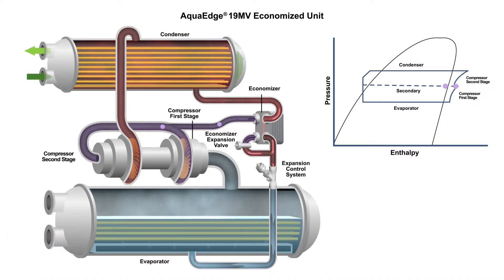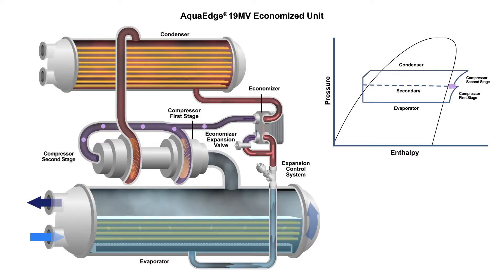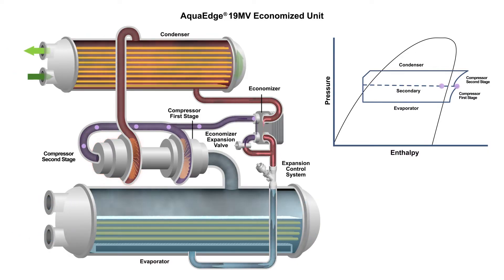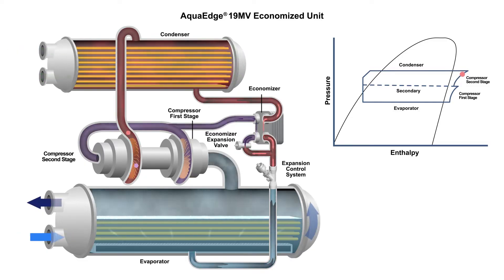Vapor leaving the compressor's first stage mixes with cooler intermediate pressure refrigerant vapor exiting the economizer's secondary flow. The compressor's second stage inlet guide vane helps equalize load between the two stages of the compressor, while the impeller accelerates the vapor, further increasing its temperature and pressure.